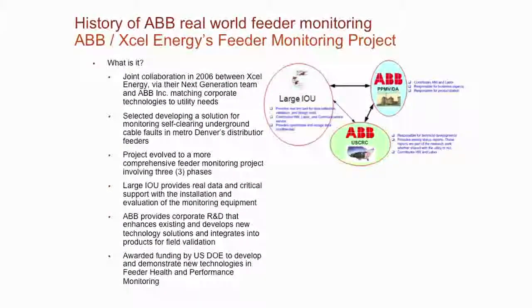This started in 2006, precisely in September of 2006, where a large utility in the Denver metro area, Xcel Energy, had some issues. They had a whole infrastructure of very aged, 30-plus-year-old underground cable faults, and they believed these were possibly showing signs of incipient failures, having problems, but there was nothing that could monitor it. When it finally gets bad enough, it's a permanent fault.